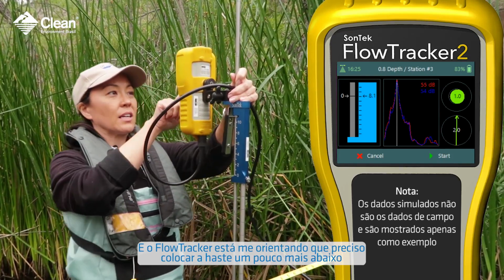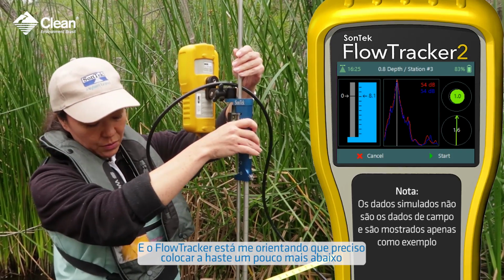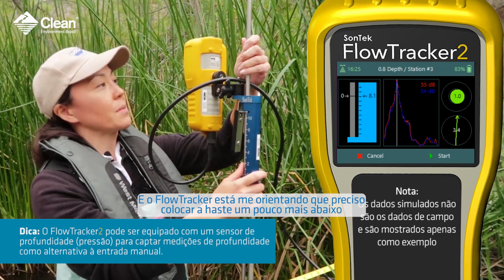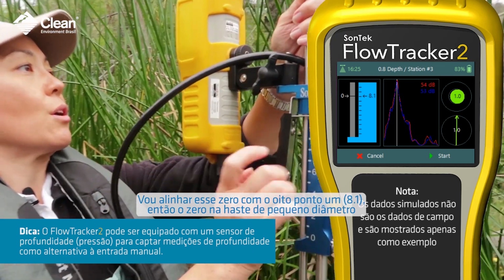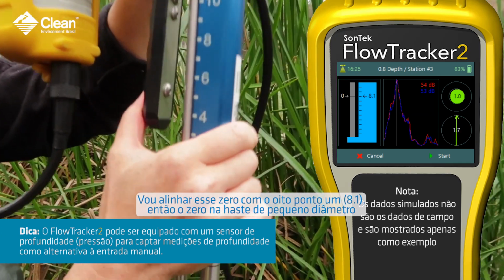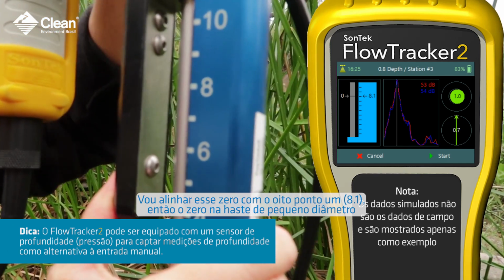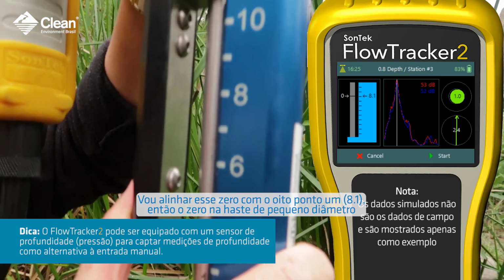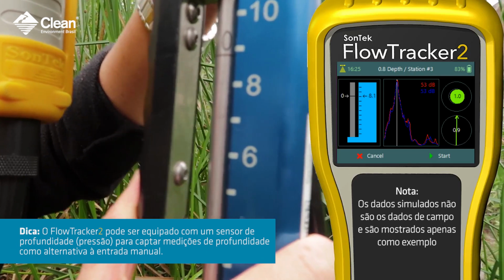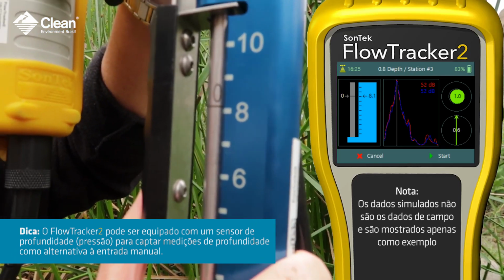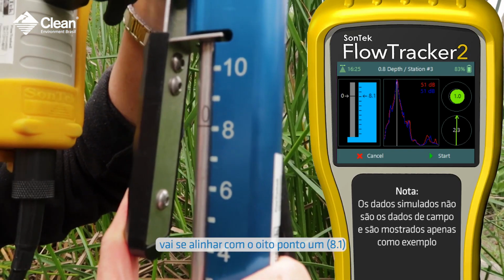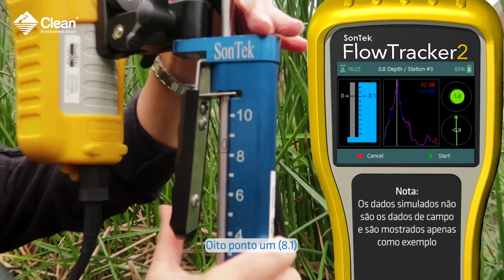And the FlowTracker is guiding me that I need to put the rod a little bit farther down. I'm going to line that 0 up with the 8.1. So the 0 on the small diameter rod, it's going to line up with 8.1.